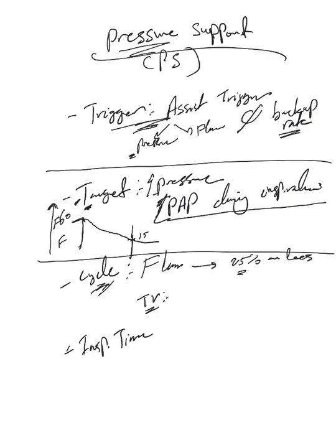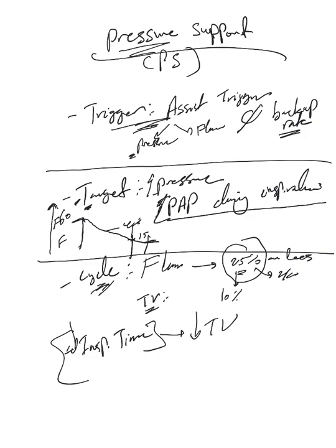Also, we can play with the inspiratory time, because inspiratory time here is not directly set. It depends on the percentage we pick here. If I make this 10%, that means it will terminate here. That means more time. If I make it 40%, that means we'll be here. That means less time. So less inspiratory time means less tidal volume, and higher inspiratory time means higher tidal volume.